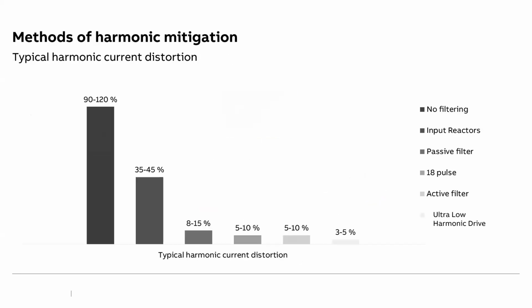I'm talking about the mitigation techniques for VFDs. The most common, easy and cost-effective solution is having a choke. Most of the advanced VFDs come with an inbuilt choke, or what we call an inbuilt DCR. These chokes restrict the harmonics to a maximum of 30%. So the 70-80% harmonics which was there now gets reduced, almost by 50%, to approximately between 30 and 40% by using a choke.